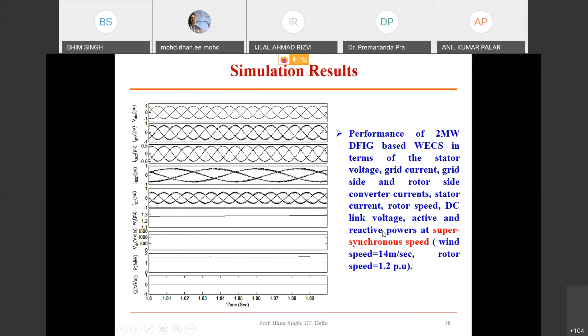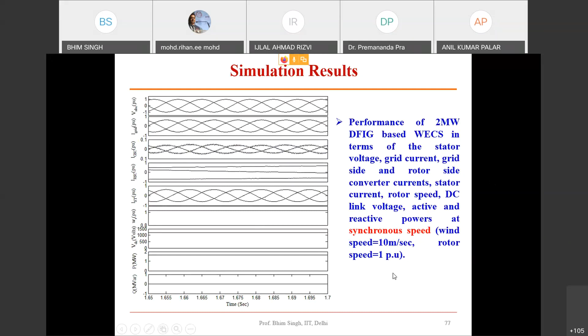And you have exactly synchronous speed. Synchronous speed means we call it 1 per unit, and you can see the rotor currents are DC currents. Are you able to follow? The grid voltage or typically the grid current, your grid side converter current, your stator current are there, but the rotor currents are DC currents at exactly synchronous speed, and it works again as a generator, like an alternator working.